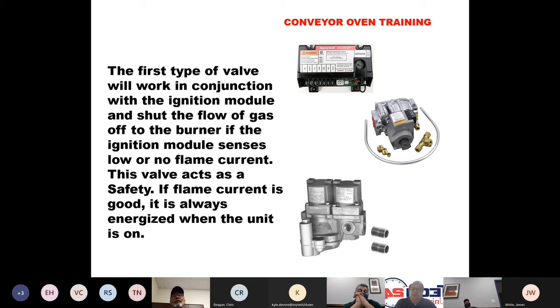So these are two examples of the first type that work with the ignition module, and they will shut the flow of gas off to the burner if the ignition module senses low or no flame current. Basically, this valve acts as a safety. If the flame current is good, it's always energized when the unit is on.